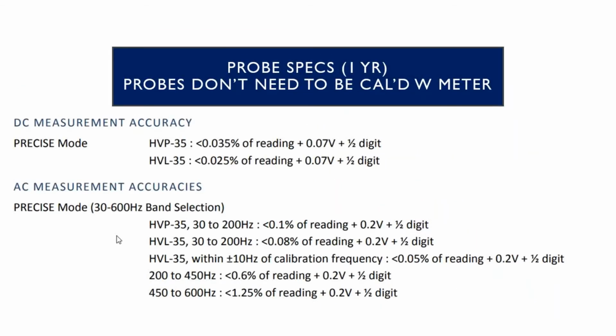By the way, the probes are smart probes, so they have all the cal data directly on the probe, and that means you don't have to send the meter and the probe in together and get them cal together. You can actually just send the probe in. And what happens is when you plug the probe into the meter, it reads it and it's got the cal coefficients. The other thing is we don't pass high voltage from the probe over to the instrument. What's really passed is a digital DC signal, and that makes it safe. If you don't want to be passing around high voltage, it just increases the chances of getting shocked.